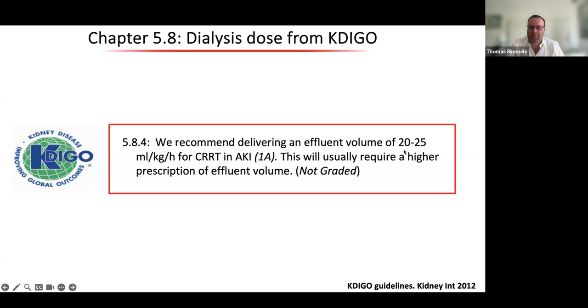What is extremely important to understand regarding the dose is that when you talk about the dose, you have to place a word in front of it. Are you talking about the prescription, or the dose really administered to your patient? Because it's totally different. If I prescribe 35 ml per kilo per hour, that's my prescription in the morning. I'm going to lose a little bit of dose because of the nursing time. When my nurses do the nursing, they stop the exchanges, they stop the therapy. They do not stop the blood flow pump, of course, but they put it in safety mode. I hope you know the safety mode during nursing. I think it's very important to use it.